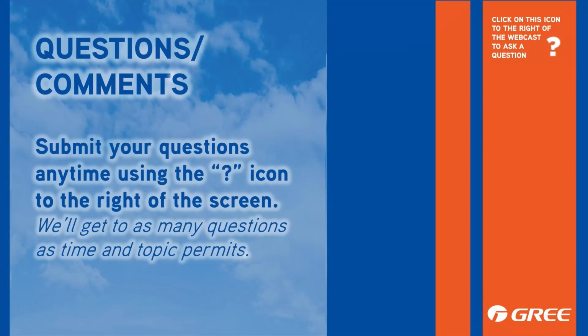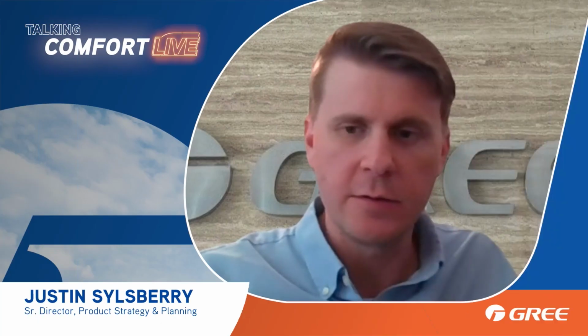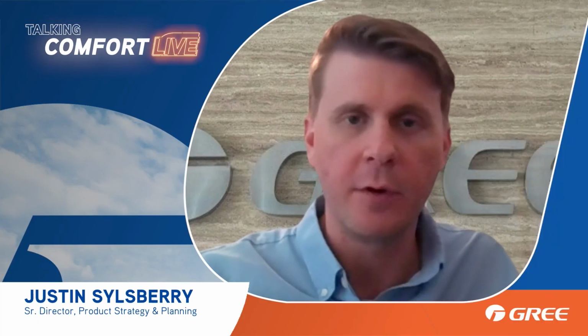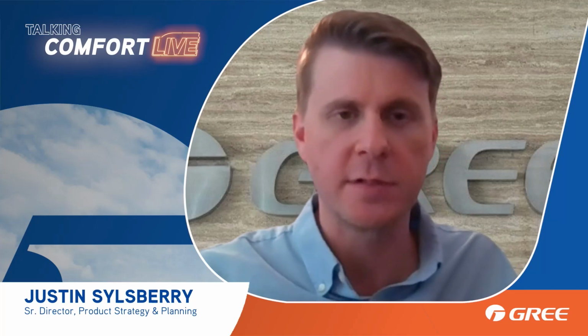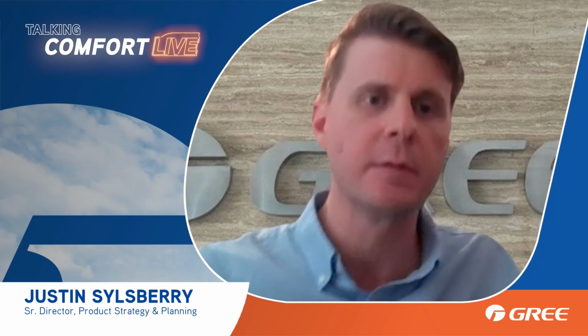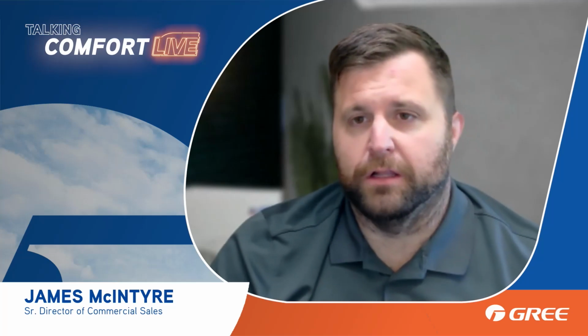Yeah, I was just going to say, I think it's a great improvement versus the last version, having the RS485 communication capability and the full variable speed capability of the indoor fan with that RS485 communication. It's just going to better ensure even more comfort for the homeowner at the end of the day versus the prior versions that were stuck in one speed with the dip switches. Right. Well, yeah, I was going to say better dehumidification. Being able to drop that fan speed also means that the system's inherently going to be running at a lower speed too. So that's going to give you a longer run time.